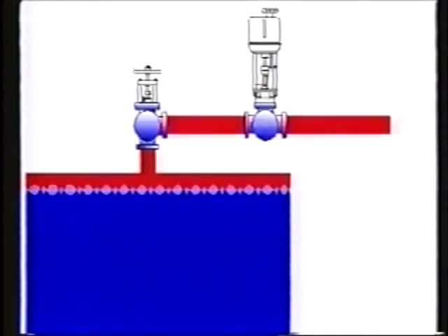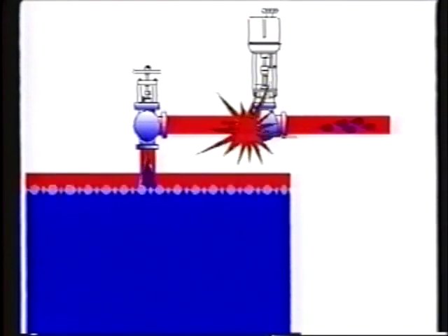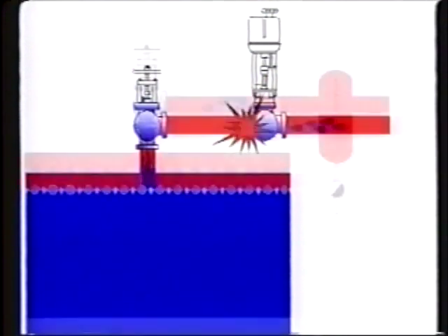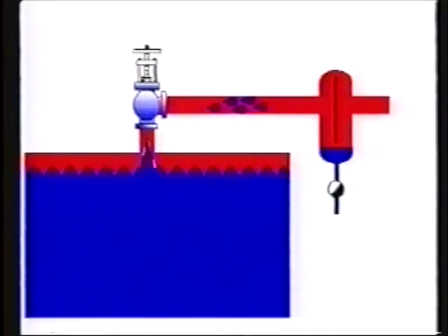If water is allowed to carry over with steam and accumulate in the steam main, it can cause severe damage to valves and fittings through water hammer and could even cause injury to personnel. Impurities in the water can also cause contamination of the steam main, control valves, heat exchangers, and steam traps.